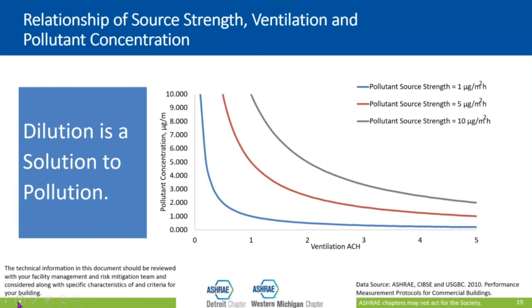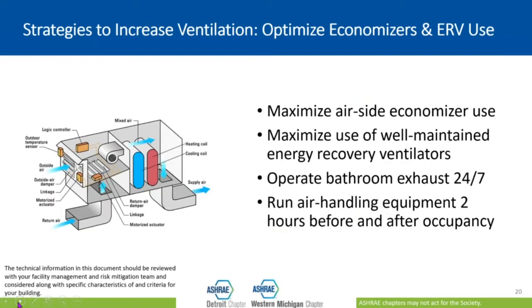So there are a couple of ways to do that. First of all, you economize your existing system. You want to certainly maximize it. If you need to, possibly reset the economizer damper minimum position to bring in more outside air, you may consider doing that. If it's already sized for 100% outside air, then that's where you want to be operating, as long as you can still meet the load.